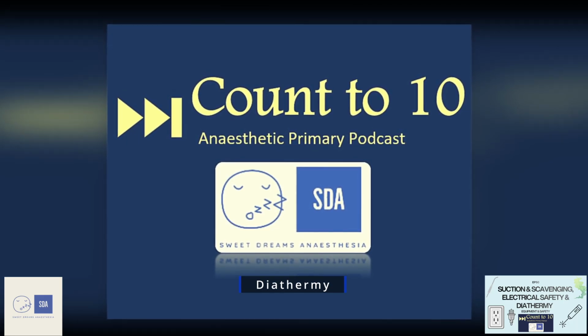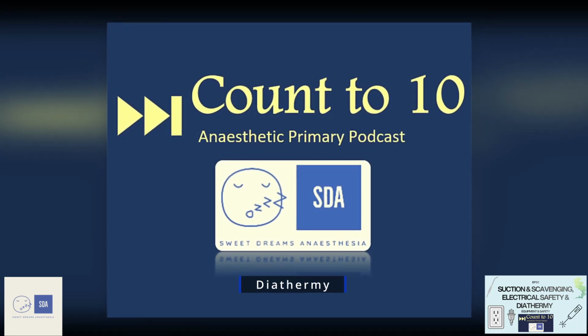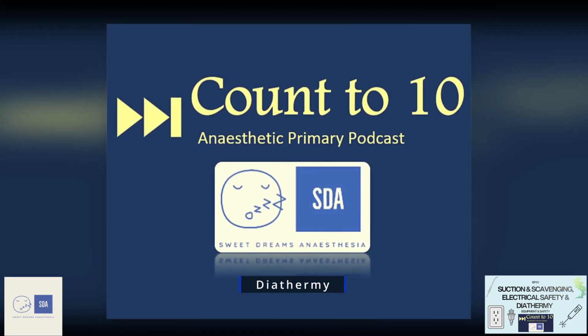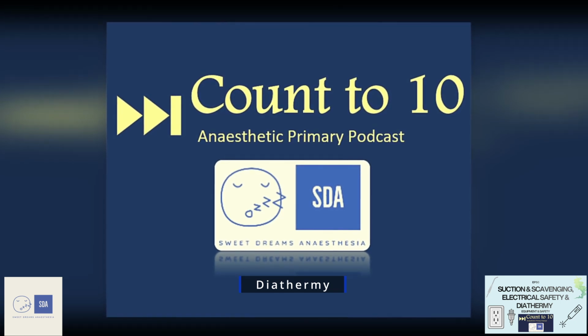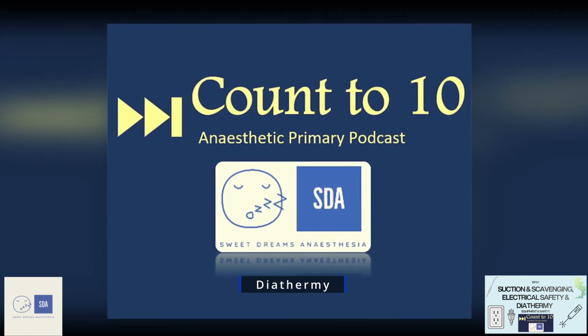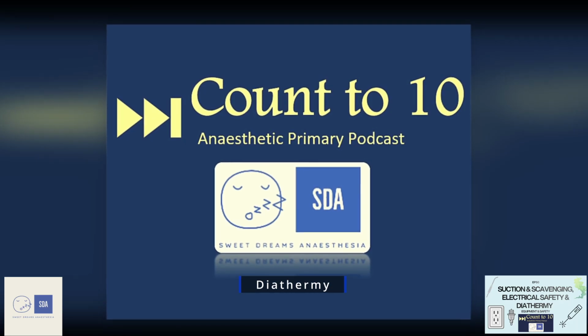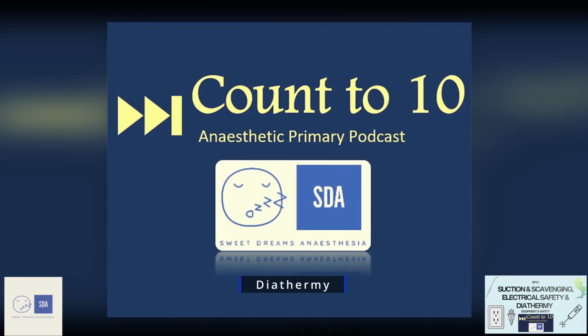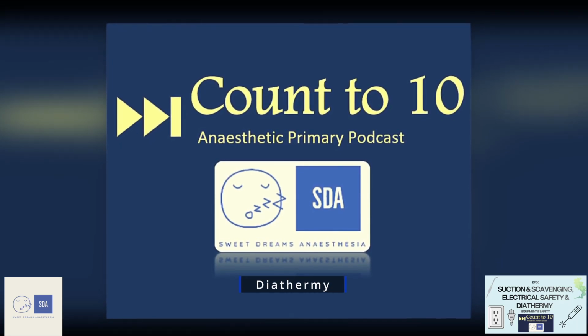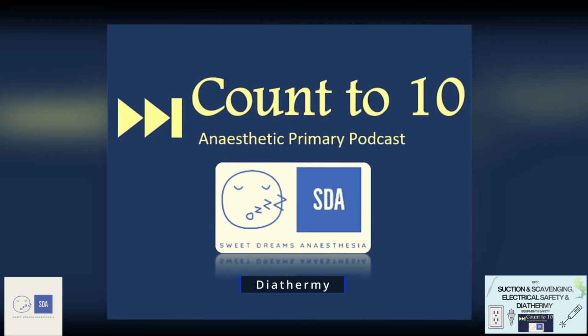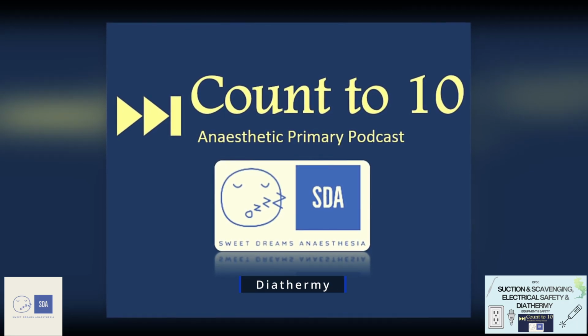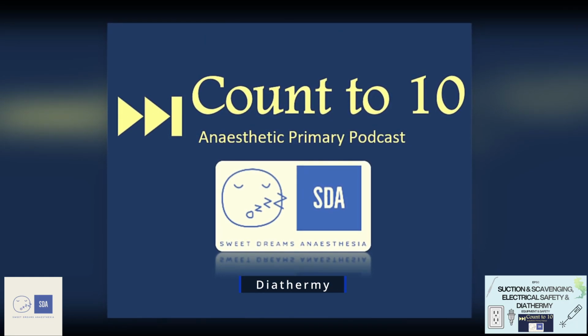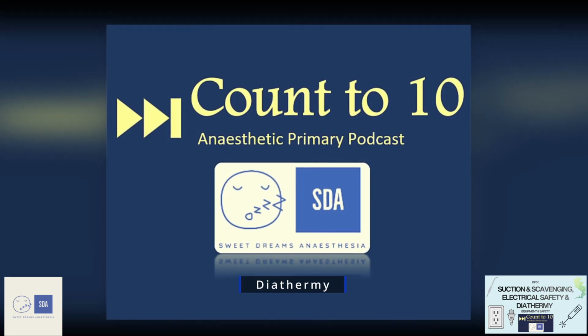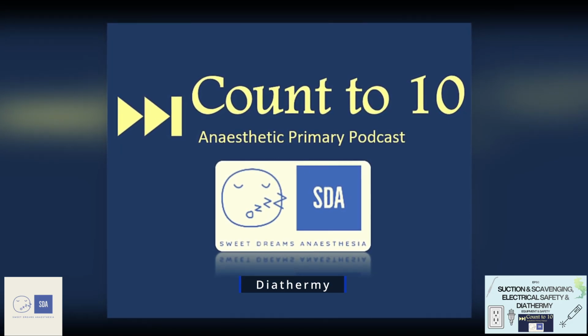The important principle you have to know here is this concept of current density. Current density is an equation which equals current divided by area. And if you have a high current density at the electrode, this causes more tissue damage. A low current density can cause heating without damage. So overall, there are two common types of diathermies out there. There's the unipolar diathermy and then the bipolar diathermy.